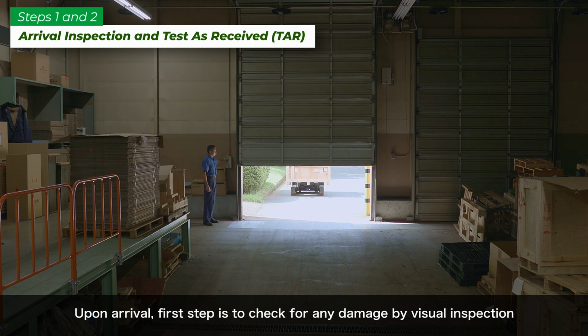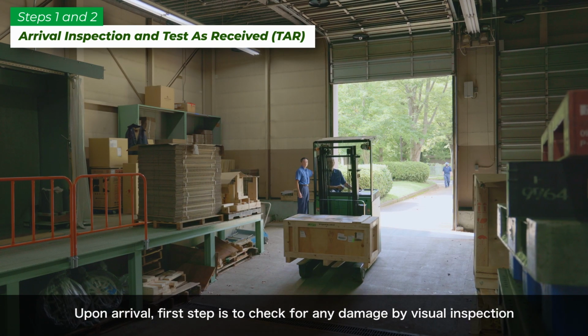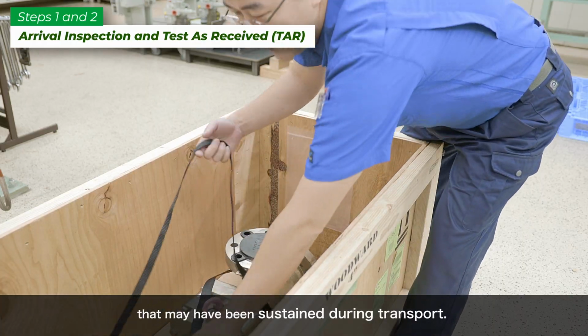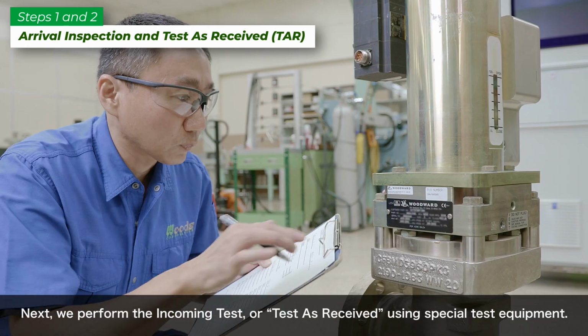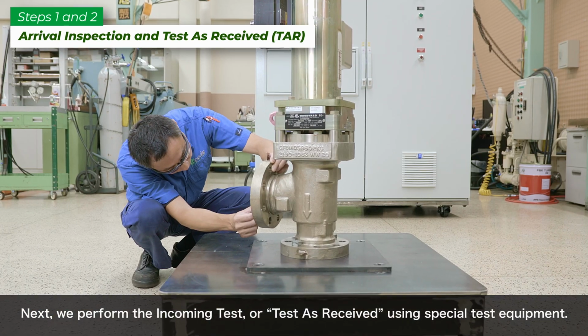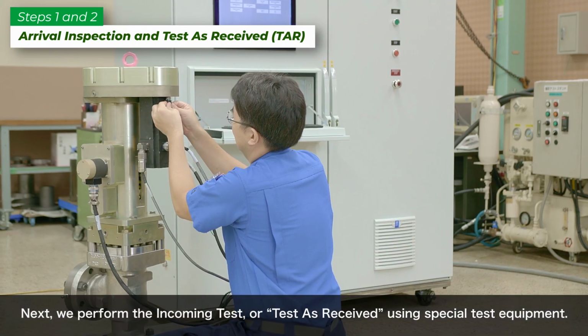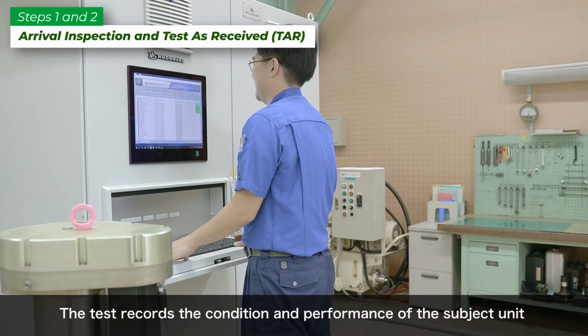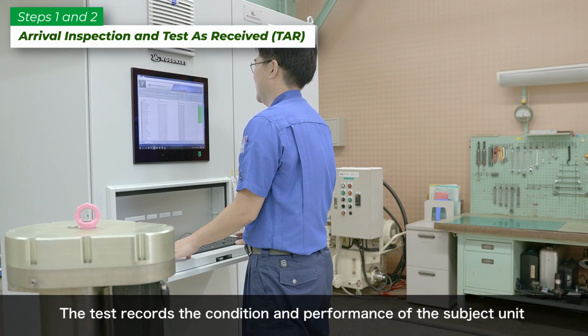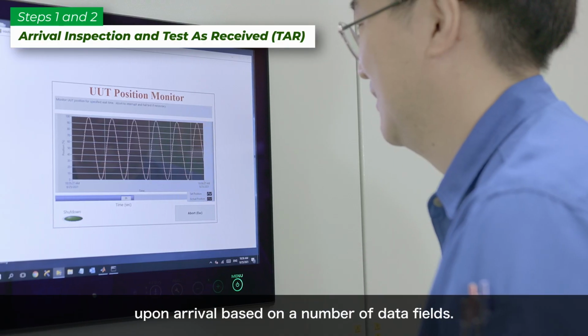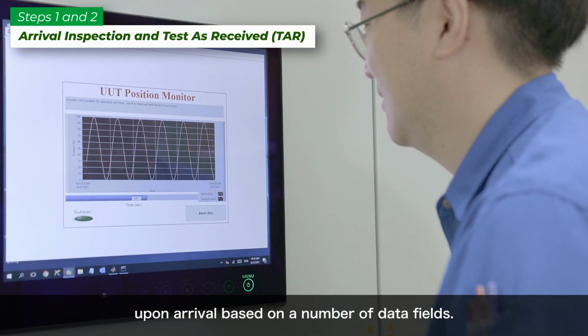Upon arrival, the first step is to check for any damage by visual inspection that may have been sustained during transport. Next, we perform the incoming test, or test as received, using special test equipment. The test records the condition and performance of the subject unit upon arrival, based on a number of data fields.